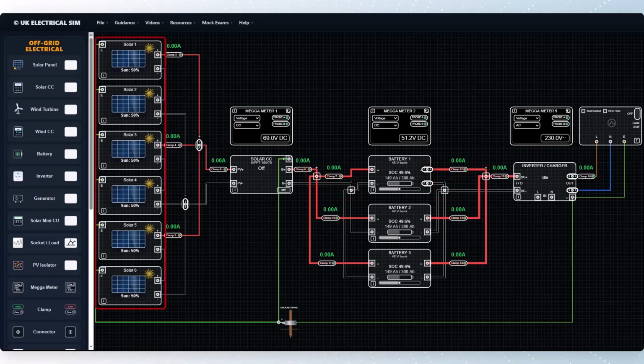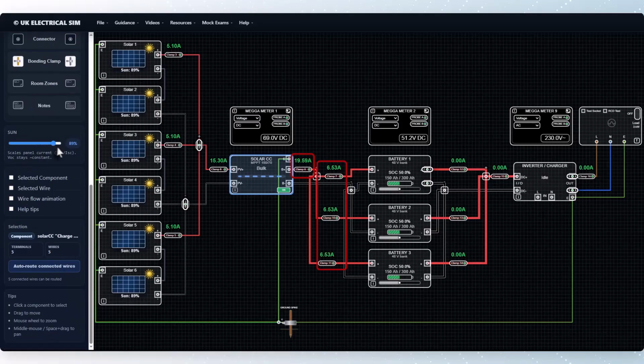On the workspace, we have the familiar 6 solar panels, a solar charge controller, an inverter charger, and a 3 kilowatt load. However, we now have 3 batteries, all wired in parallel. If we switch on the charge controller, we can see it charging in bulk mode, with around 20 amps of charging current split between the 3 batteries.